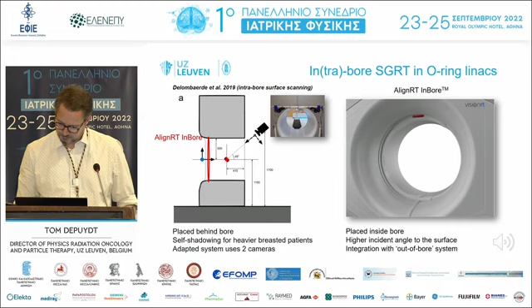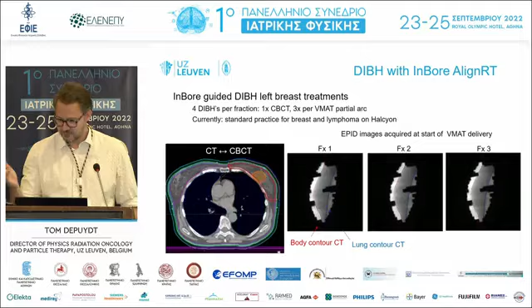And we installed these devices as well, and we started a study, but at the moment this is standard practice for breast and lymphoma cases in Leuven in the Halcyon system. And you see excellent agreement based on a deep inspiration breath hold cone-beam CT versus deep inspiration breath hold CT. And you also see, for the fractions we captured with the EPID, the beam effect of the first monitor units delivered for the VMAT, and you see a very good agreement for each fraction that is really reproducible from day to day for these fractions.